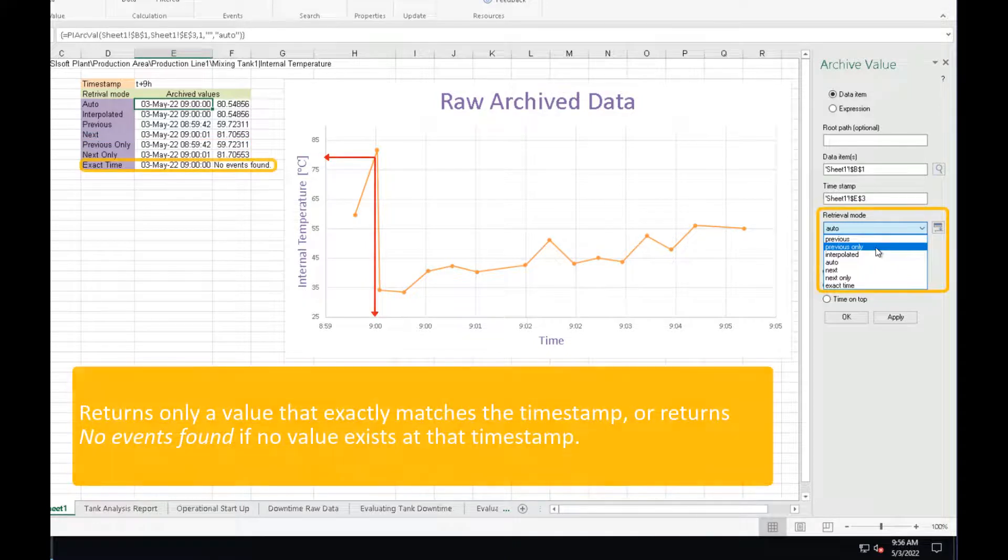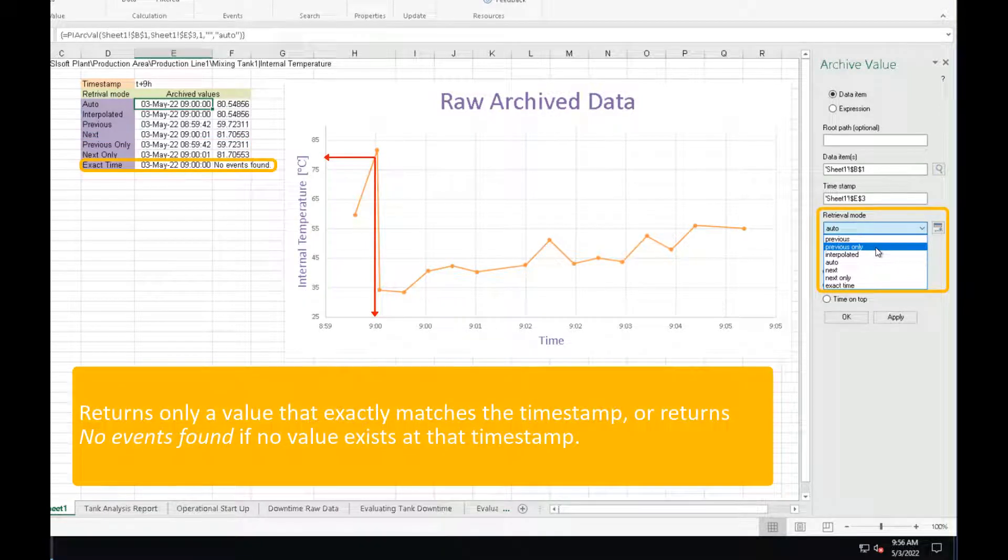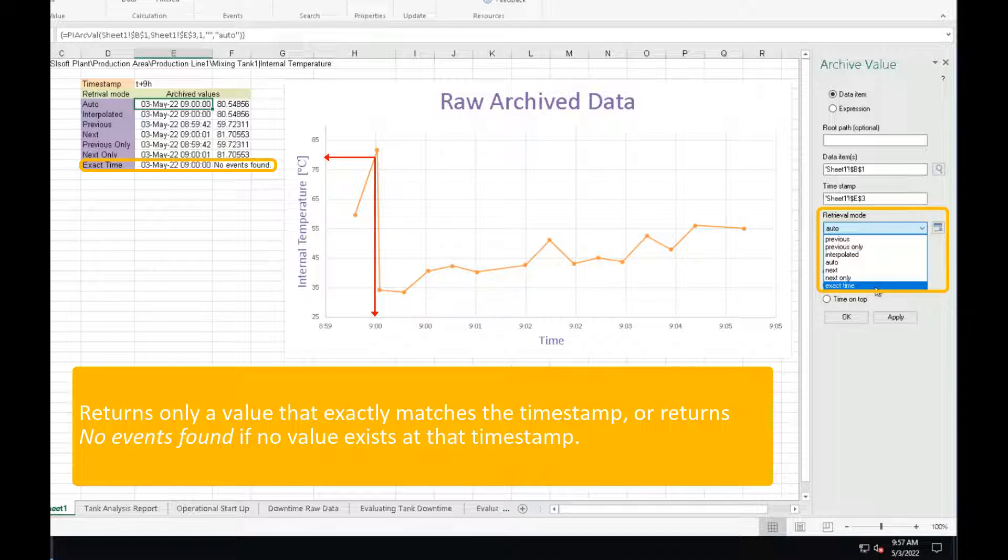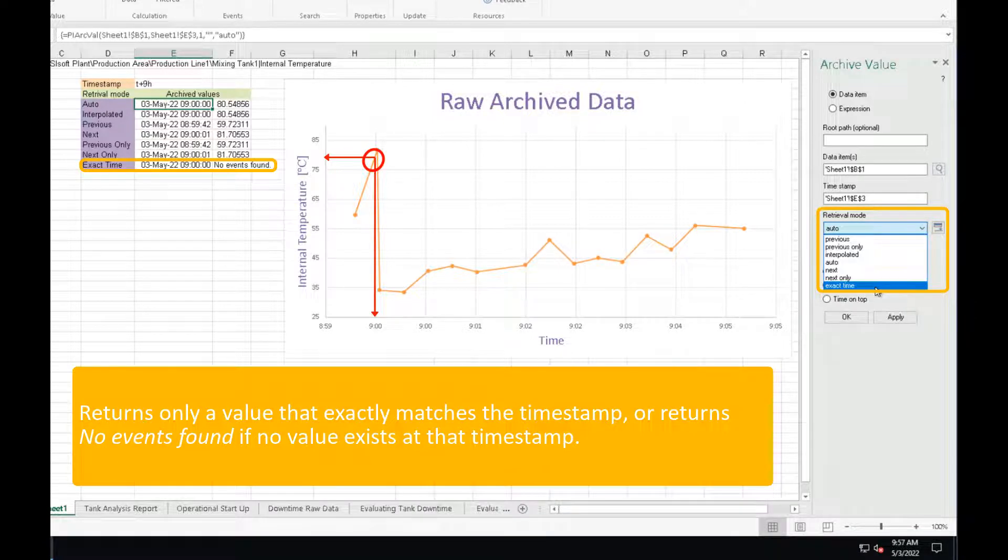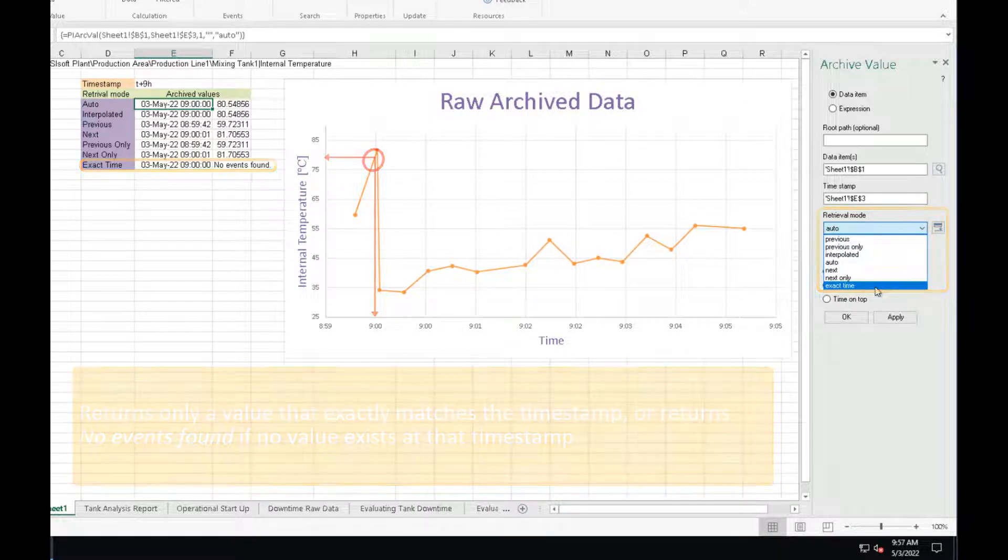And the last mode, the exact time retrieves the value if and only if an archived value exists at that exact timestamp down to the second. It returns no events found if no value exists at that timestamp.